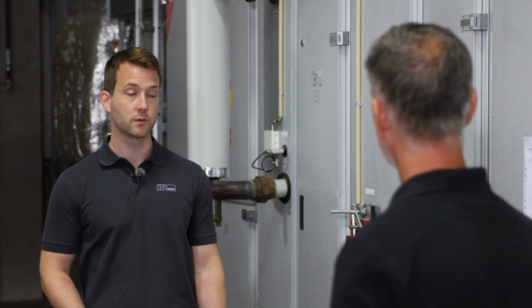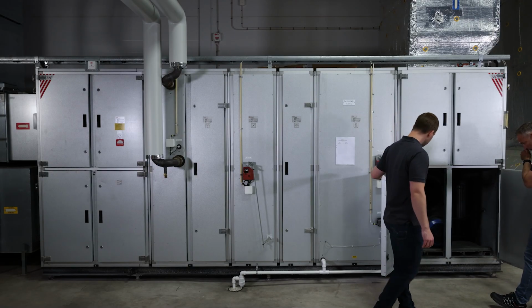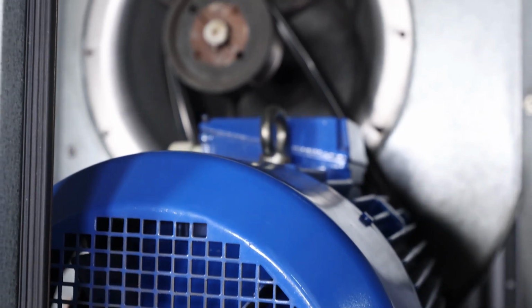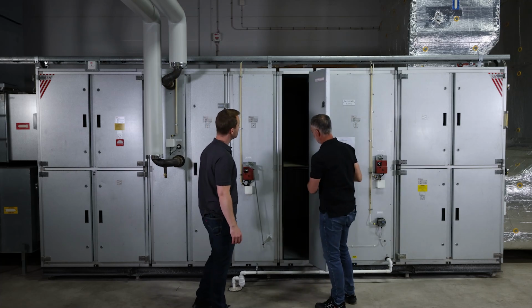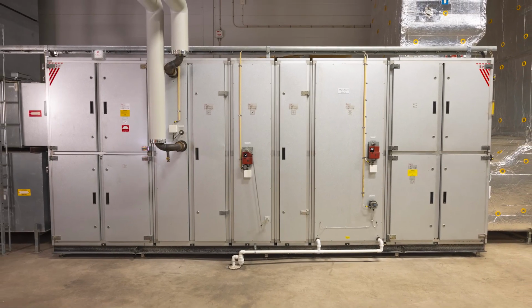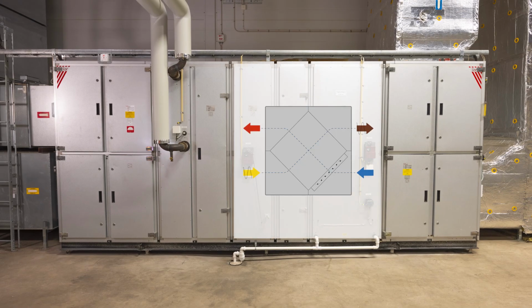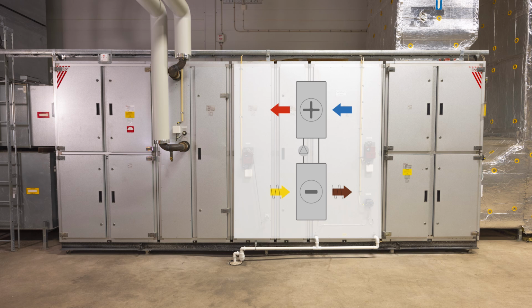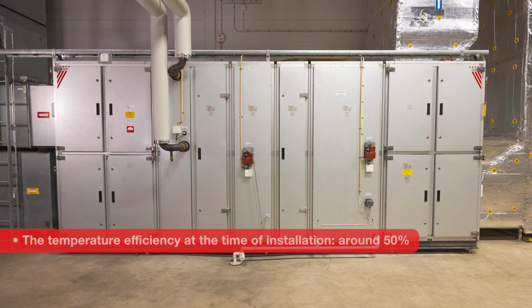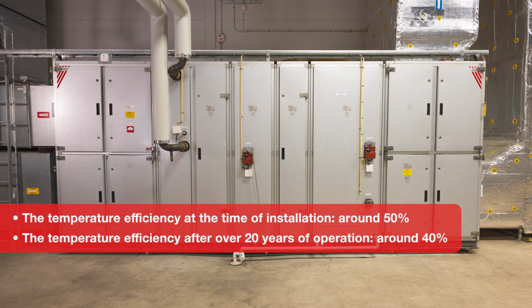What is the airflow? Well, it's 20,000 cubic meters per hour. Here we see they're belt-driven fans, and the SFP value at that time used to be around 3.5. We have a heat exchanger with around 40% efficiency. In the 90s, plate heat exchangers or run-around coils were most often used as heat recovery units. At the time of installation, the temperature efficiency was around 50%, and after more than 20 years of operation, it may have been reduced to around 40%. What are the operating hours? It's 3,500 hours per year.